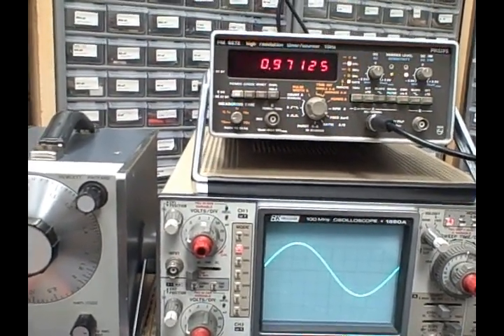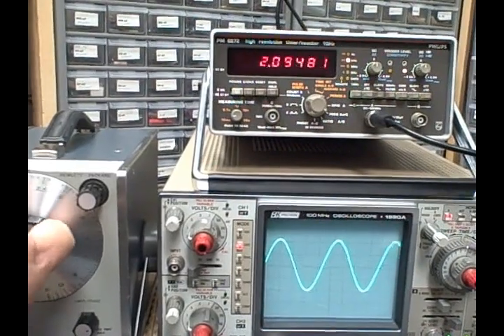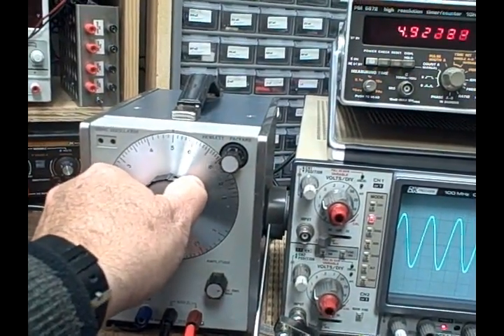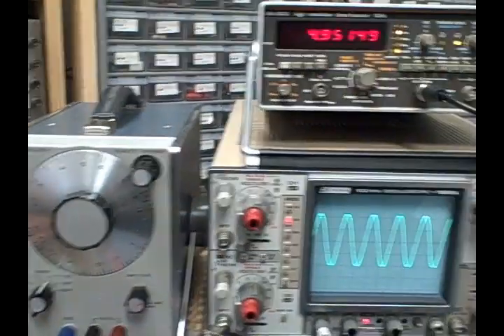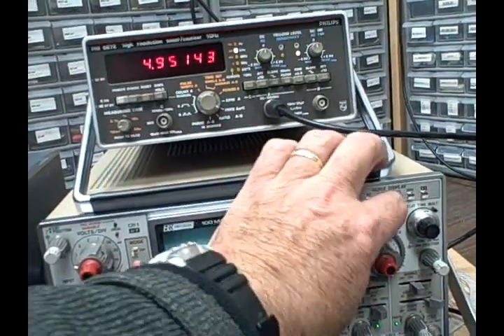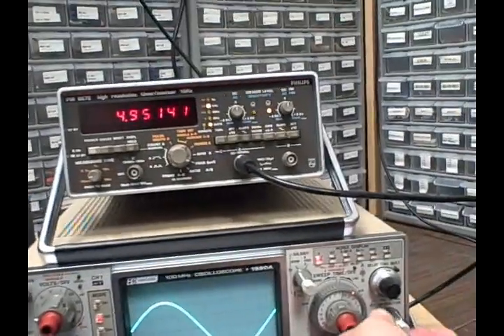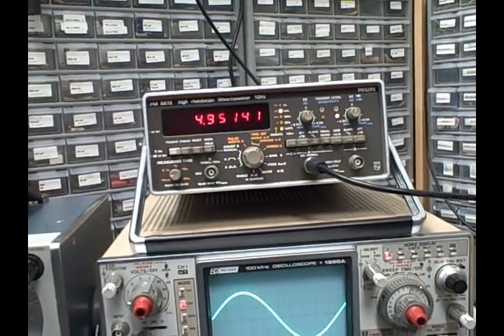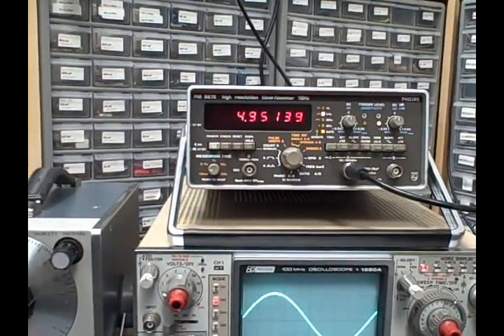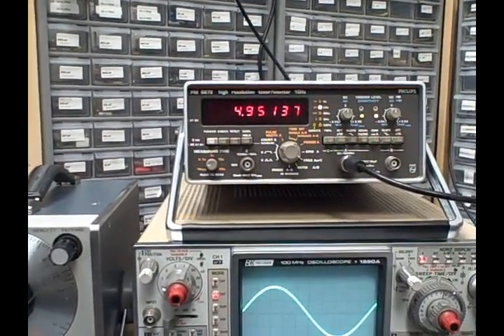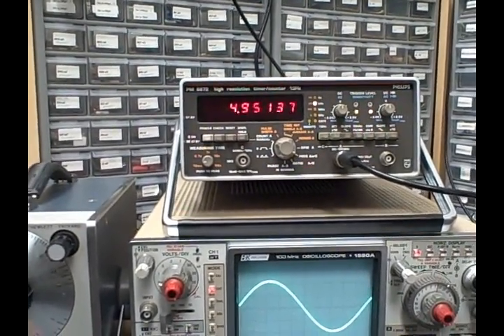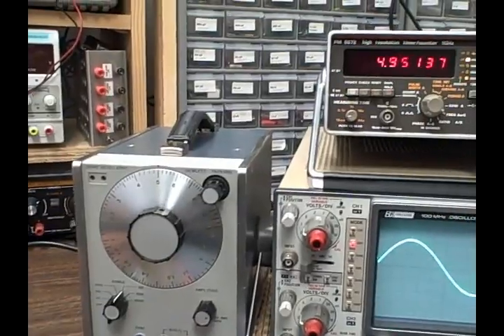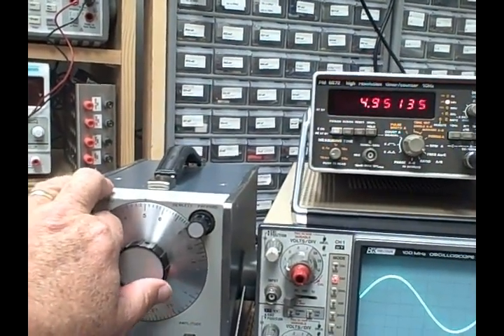Okay. And we'll take her to the next frequency, go up to 5, right about there. And try and get 1 trace on here, there. 1 trace in 10 divisions, 20 microseconds per division, so that's 200 microseconds, which would make this 5 kilohertz. We've got 4.95 kilohertz, so we are about 50 hertz out of 5 kilohertz as far as the dial. We got that close, which is about 1% roughly.